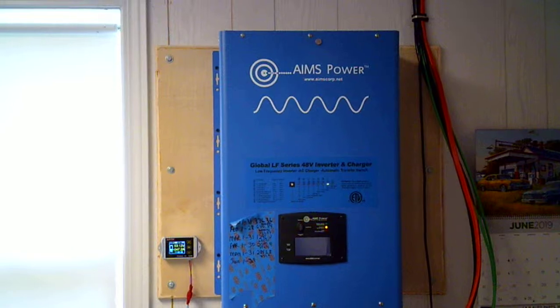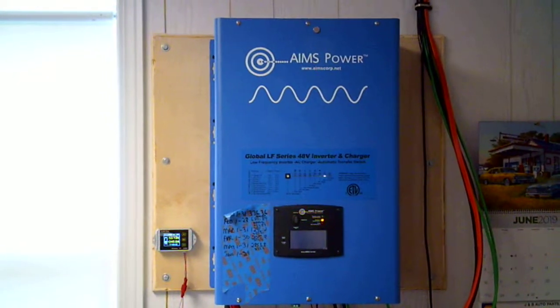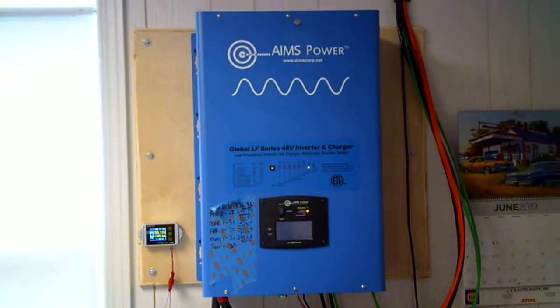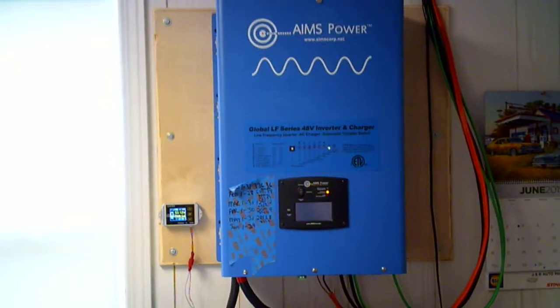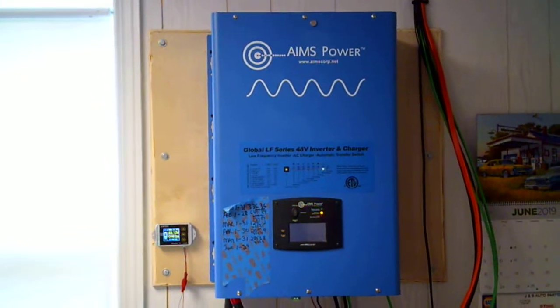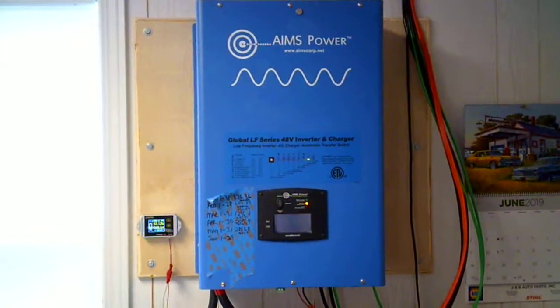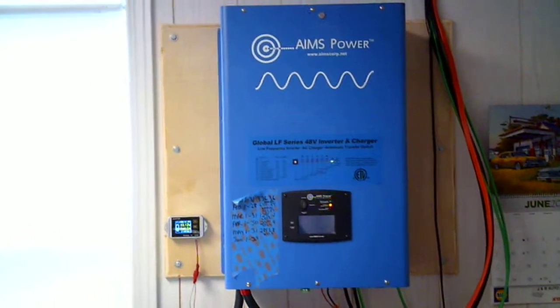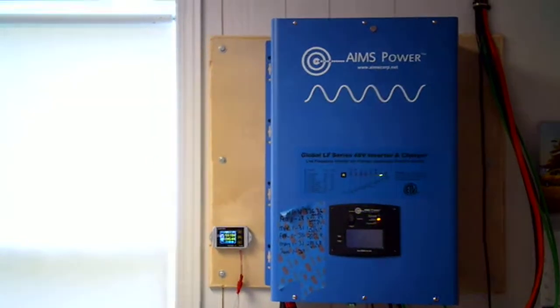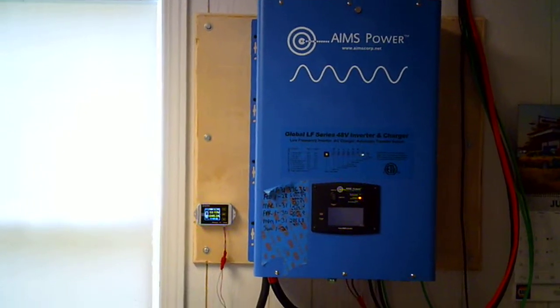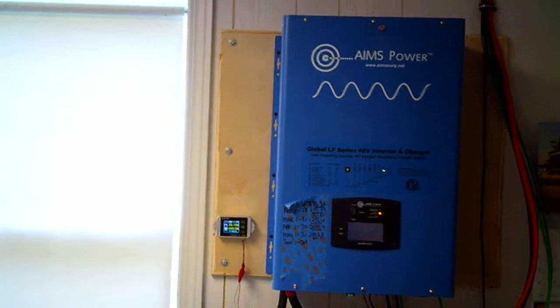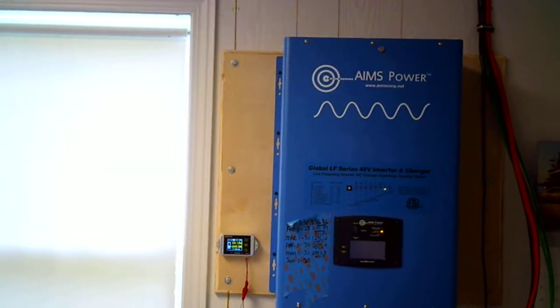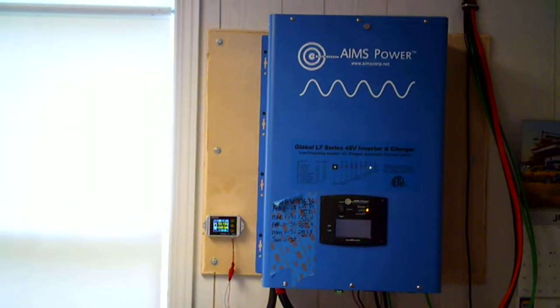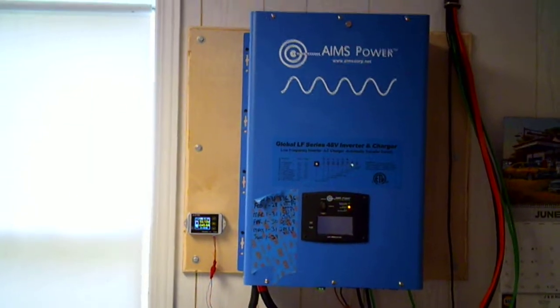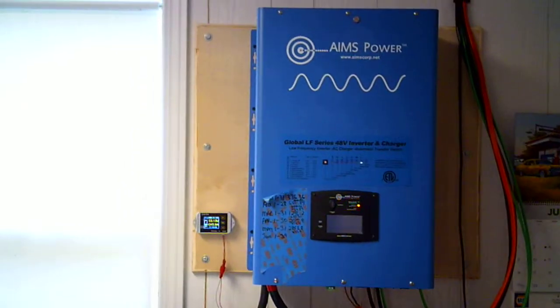The output isn't the best. Instead of doing the 220 to 240 that the grid provides, this does about 220 to 230. So all my 110 circuits, like the lights I've got on in here now, instead of getting 124 volts like they'd normally see from the grid, they only get about 110 to 114, and that fluctuates and makes the lights kind of flicker, which is annoying.